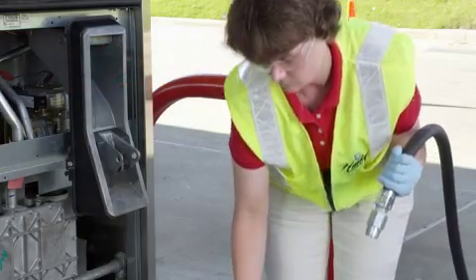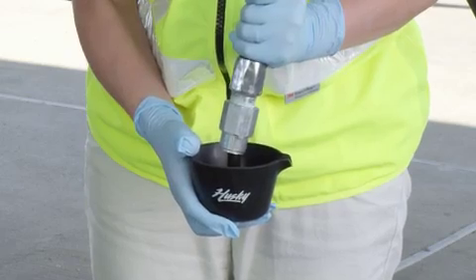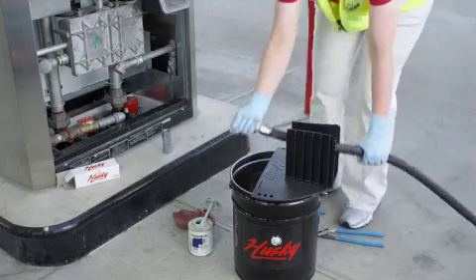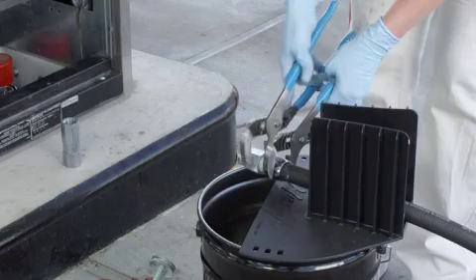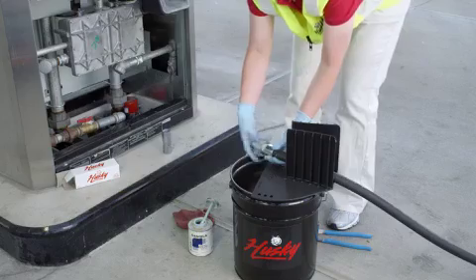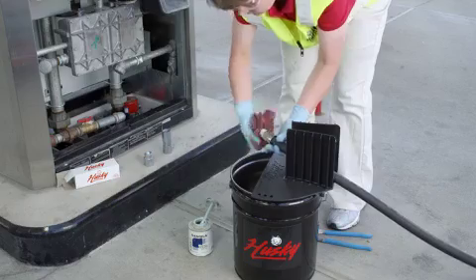Once the fueling point has been taken out of service, relieve the pressure on the long hose by pushing in the check valve using a Husky safety breakaway drain cup. Carefully remove the long hose half of the safety breakaway. Wipe clean the long hose threads and apply a thin coat of pipe sealant.